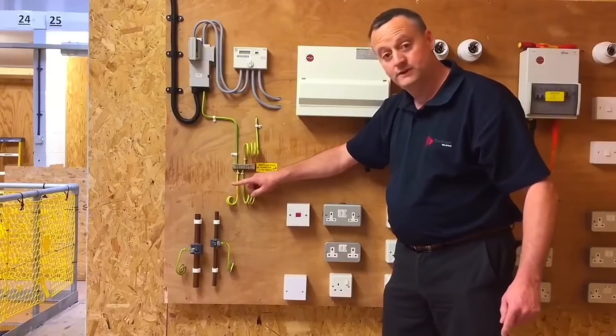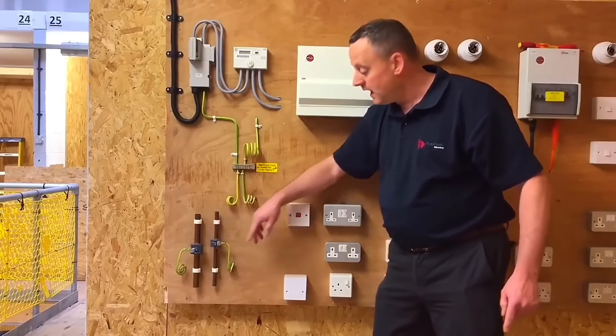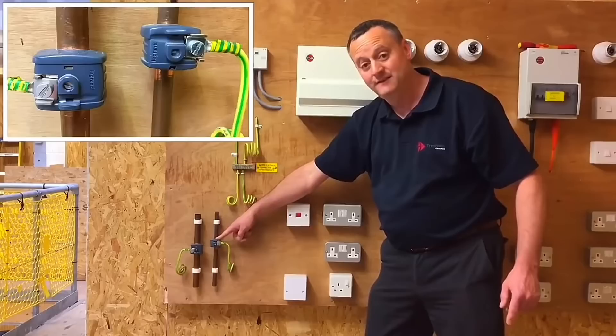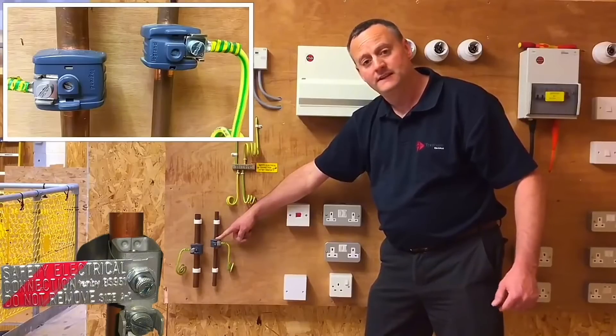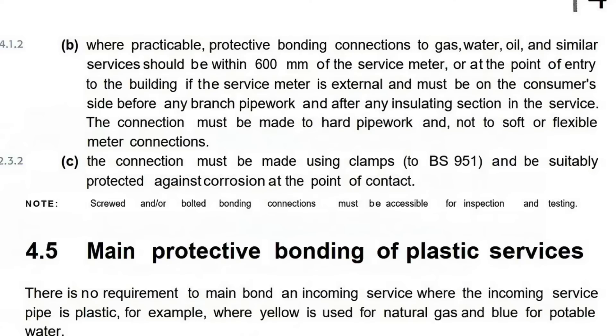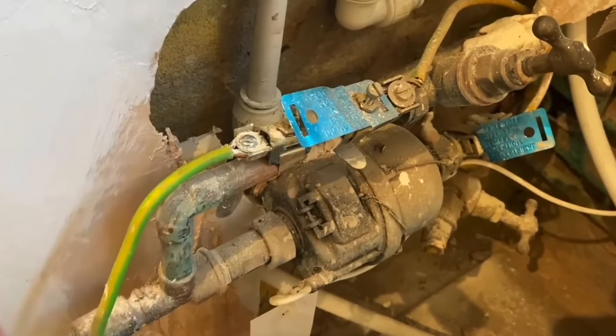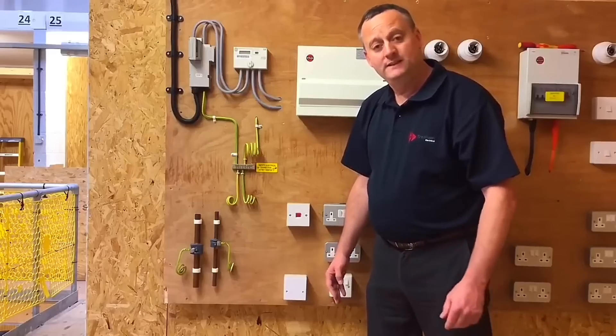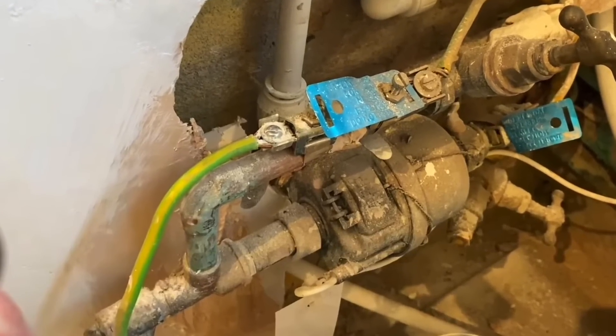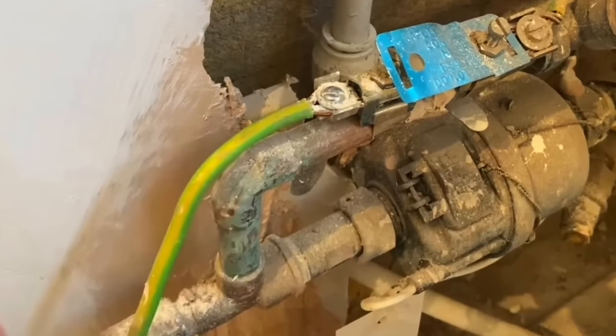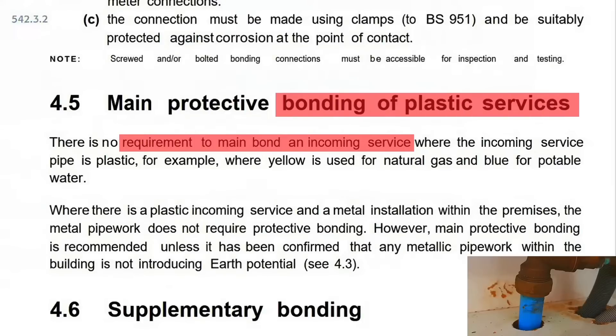The protective bonding conductors, simulating going to gas and water, are terminated. They must be terminated with a clamp that says 'Safety Electrical Connection — Do Not Remove'. That clamp is to be terminated within 600mm of the incoming point — in other words, consumer side, after the water stop tap, after the gas meter, within 600mm of entering the installation. However, if there is a T-piece — what the regulations call a branch — the clamp must be made before that branch if it is under 600mm. So it's within 600mm or before the first branch in order to make these connections.